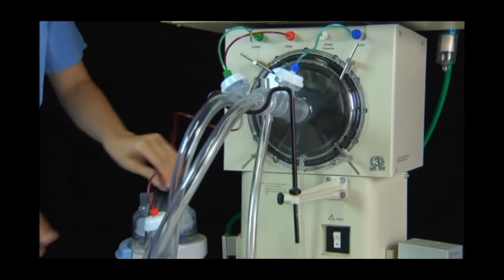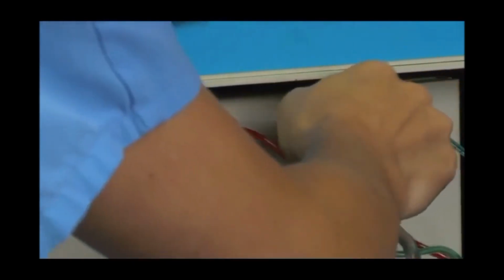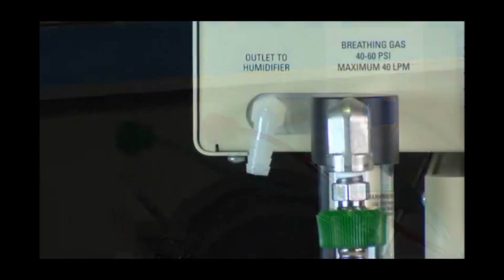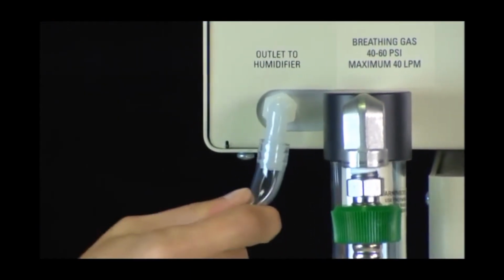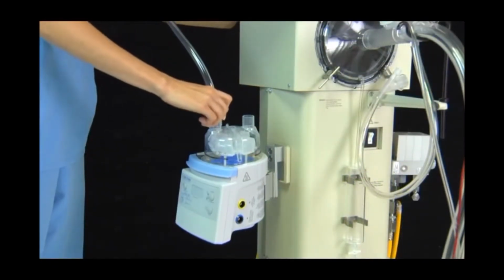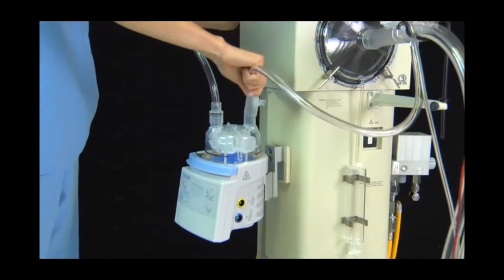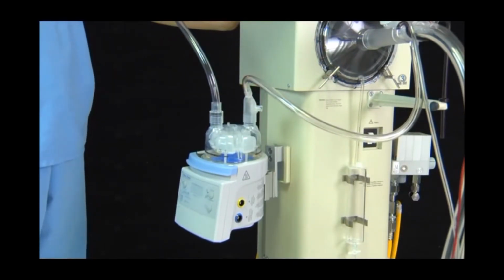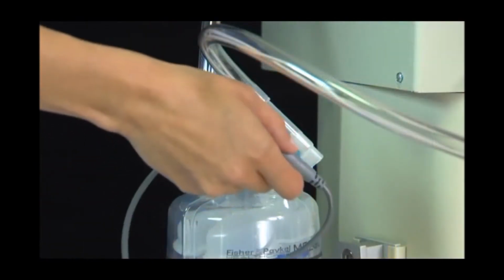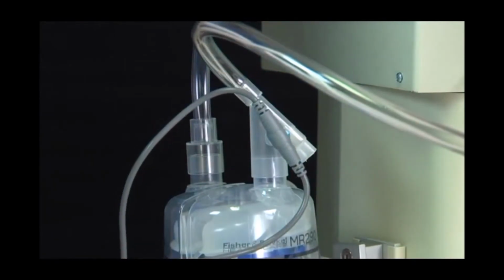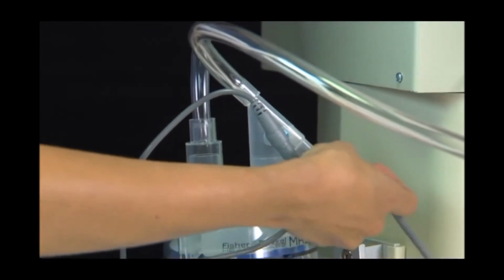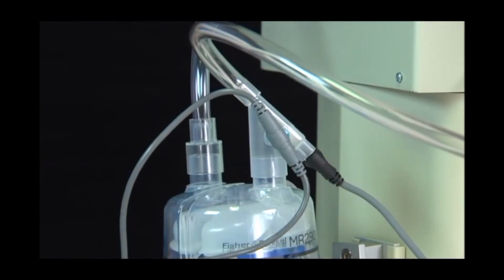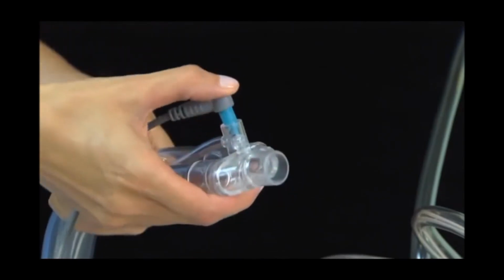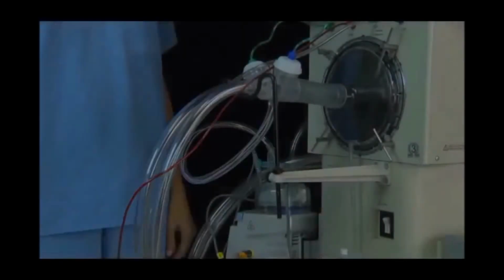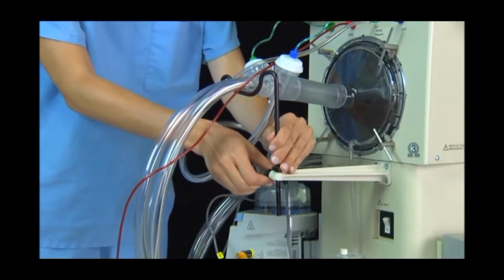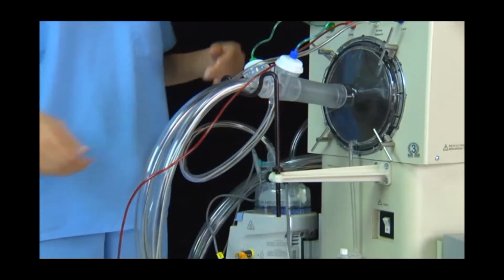Attach the pressure sensing line to the lower fitting marked airway pressure. Attach one end of the connection tubing to the port marked outlet to humidifier on the rear panel of the ventilator. The opposite end of this tubing should be connected to the inlet of the humidifier. Connect the bias flow tube from the ventilator circuit body to the outlet of the humidifier. Insert the chamber temperature probe into the port on the connector from the output of the humidifier. Connect the heated wire to the heater wire output from the humidifier. Insert the proximal temperature probe into the tapered opening near the patient Y. Use the cradle adjustment to maintain the proper circuit height and angle. The proper angle should allow condensate to run downward into the water trap.